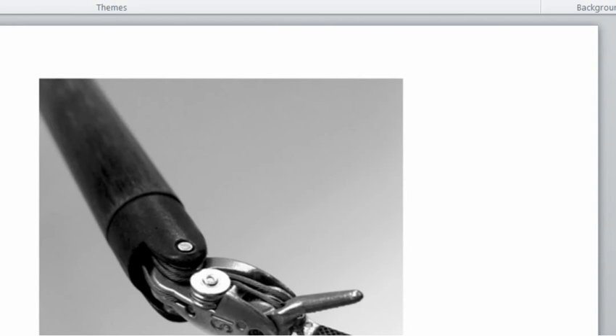For an application in MAS, this sensing method was investigated with a specially designed laparoscopic grasper. A DC motor was used in this case to actuate the grasper jaw through a cable-driven mechanism. With a calibration rule, the grasping force was calculated from the amount of current applied to the motor. Although this method offers a simple way of measuring the force, it does not provide very accurate measurements since the force is not directly measured. Its value is just estimated from the current of the motor, and as found in several experiments, the actual force exerted at the instrument was somewhat smaller than that estimated from the current measurements.